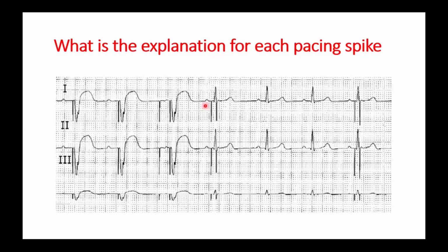Is there a difference between sensitivity of unipolar and bipolar in any machine in the atrium? Yes. Sometimes you can go down in bipolar to like 0.3, but in unipolar you cannot go down except to 0.5. So this is the difference in going down with the value of the sensitivity in order to make the atrial channel more sensitive. So you measure the P wave sensitivity in unipolar and in bipolar mode, and then you decide what to do in order to avoid this. Okay, next example.